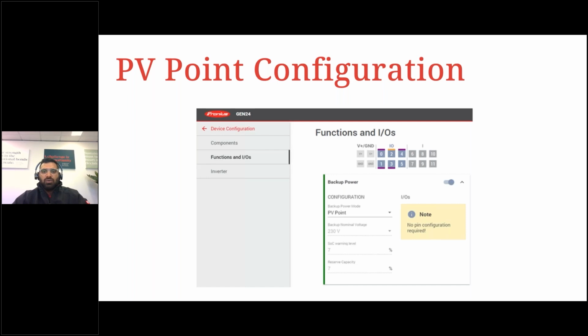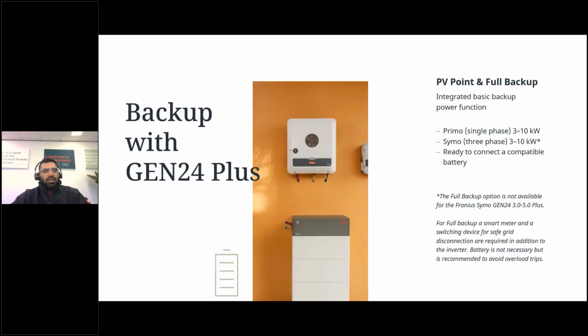Under functions and IO, you can turn on backup power mode and set the full backup to PV Point. So backup power mode can be set to PV Point, but of course you can also activate this function when you initially commission the inverter. It is one of the steps under product where you can turn on this backup power function.